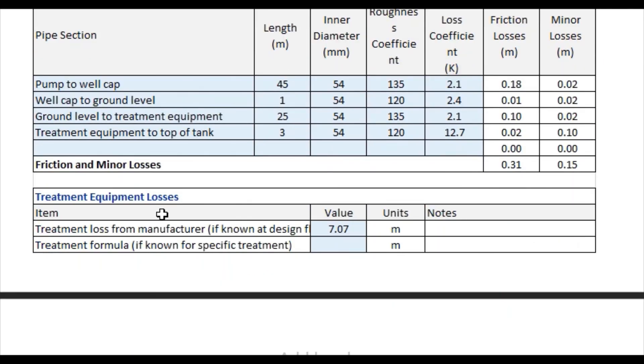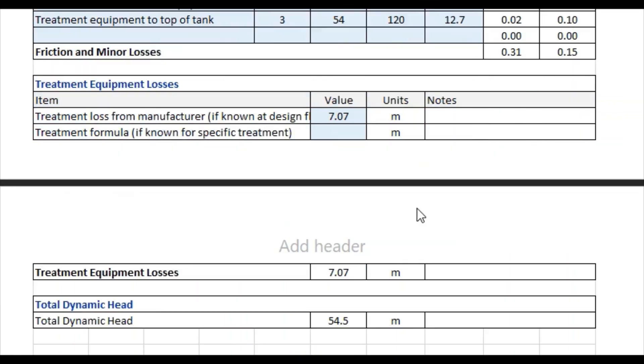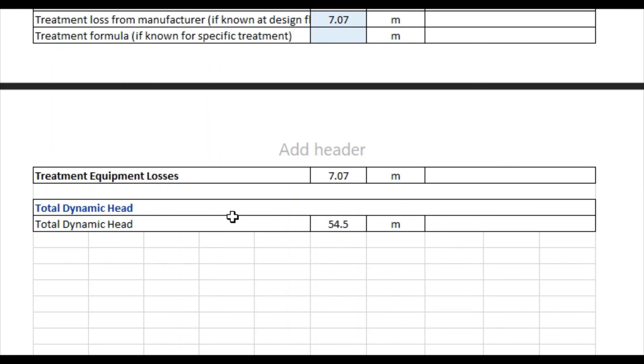In this case, our estimated treatment loss from the manufacturer is 7.07 meters. Finally, we calculate total dynamic head by adding together our static head, friction losses, minor losses, and treatment equipment losses. For this example, we get a total dynamic head of 54.5 meters. And that's the end of step three.